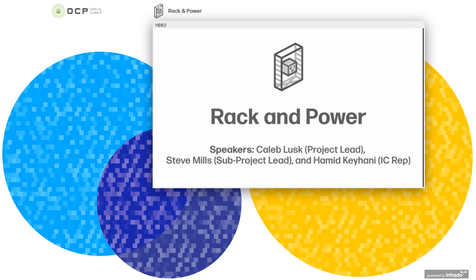It is about 50 millimeters wide and is placed directly on the power shelf. If you look at either the 1U or 2U power shelves, there is one on one of the sides, which is actually the communication with the rest of the system connects to that, and then it goes to the top of the rack. So please go back and look at the presentation that we had earlier today. You will see it there. It's on the front, so it is serviceable from the front with the card edge connector.